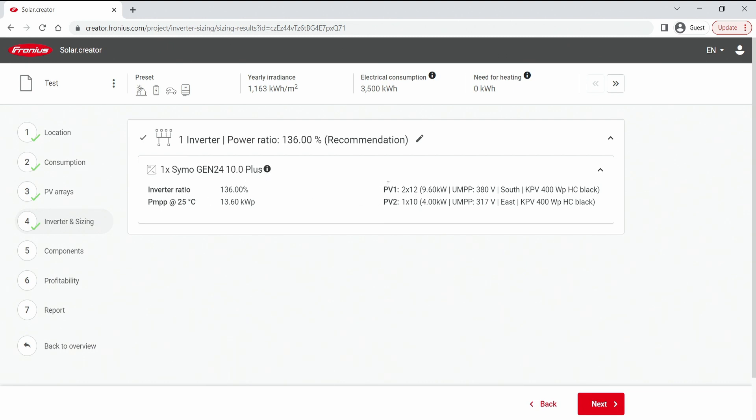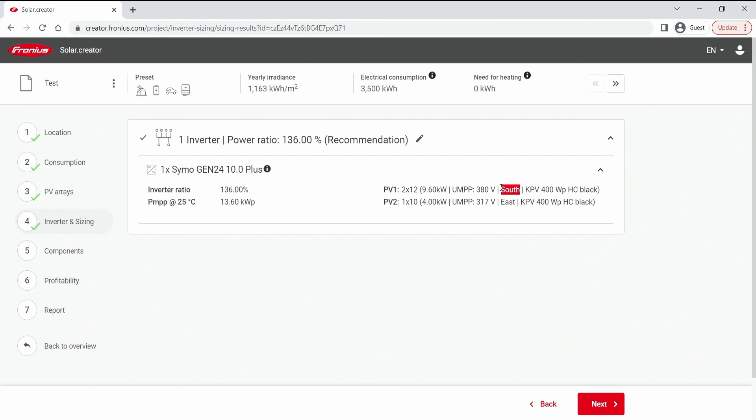We can see now how it's linked. So we can see PV1 is MPP tracker number one with two strings and 12 modules which gives me the 9.6 kW peak on the south orientation. And on the second MPP tracker we have 1x10 modules which gives me 4 kW on the east orientation.